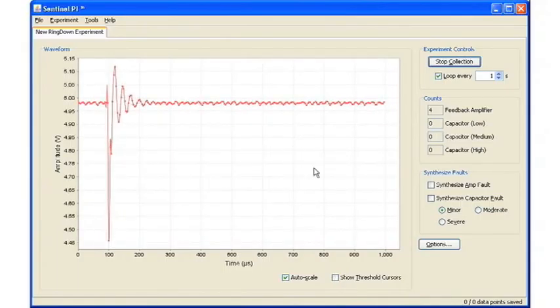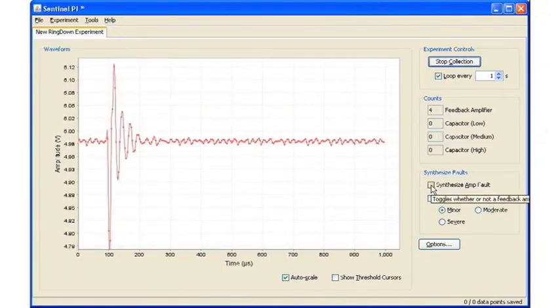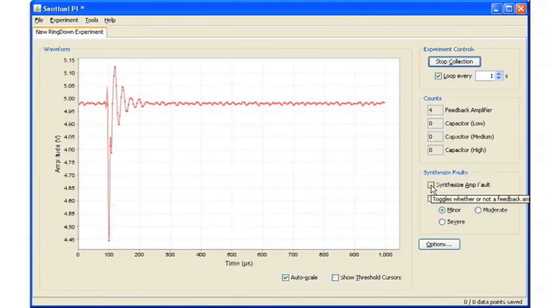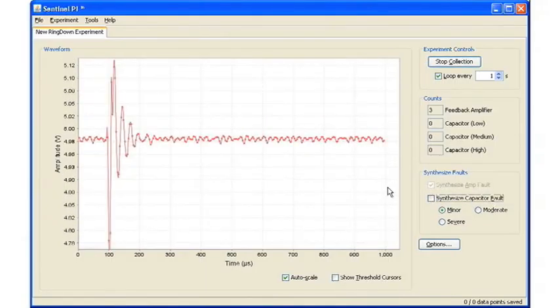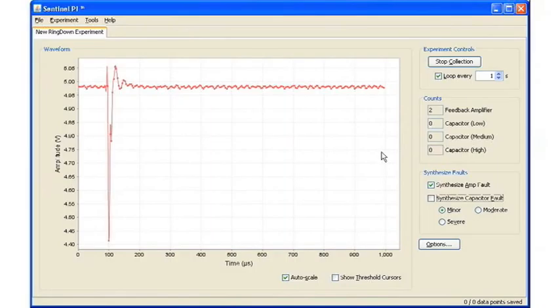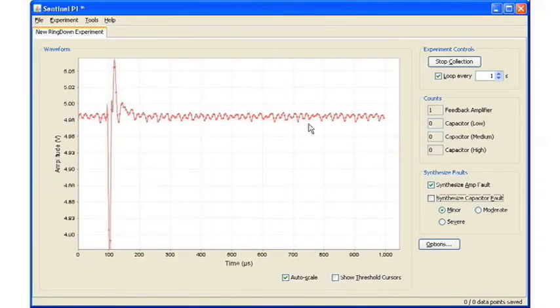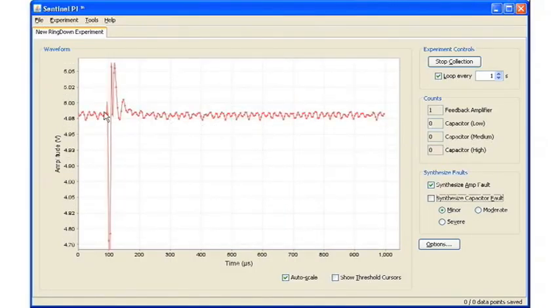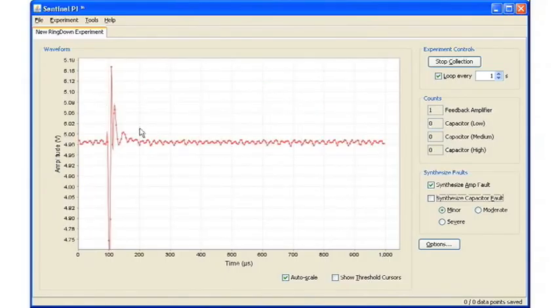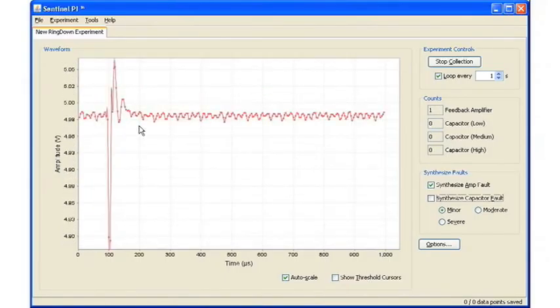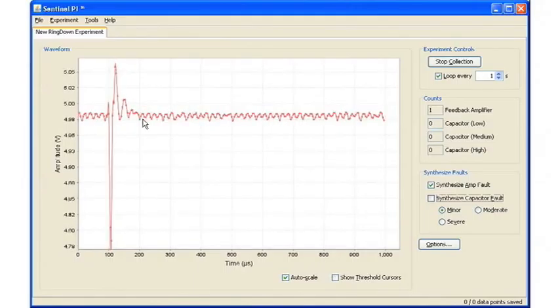The first fault we'll look at is the amplifier fault. To synthesize it, check the Synthesize Amp Fault box, and you will see a change in the ringing response of the power supply. An amp fault causes a very overdamped response of the supply so that it returns to regulation more quickly than expected.